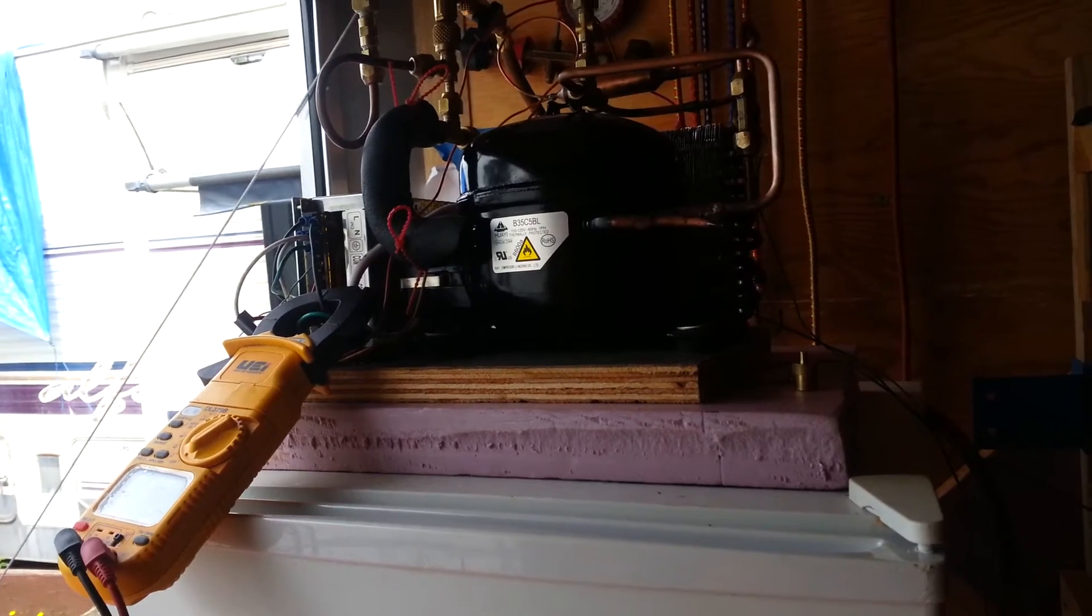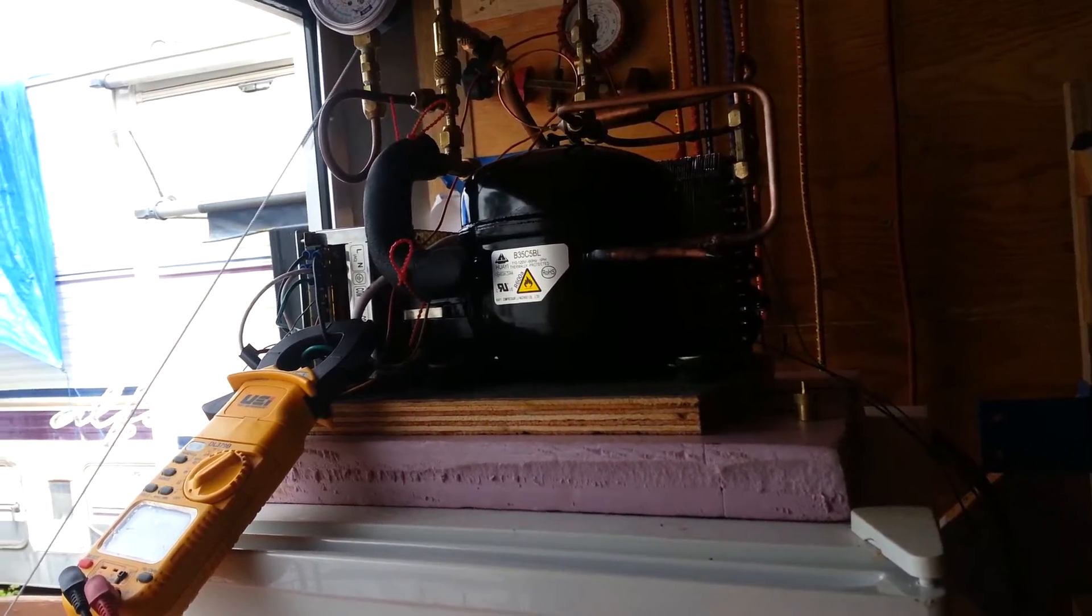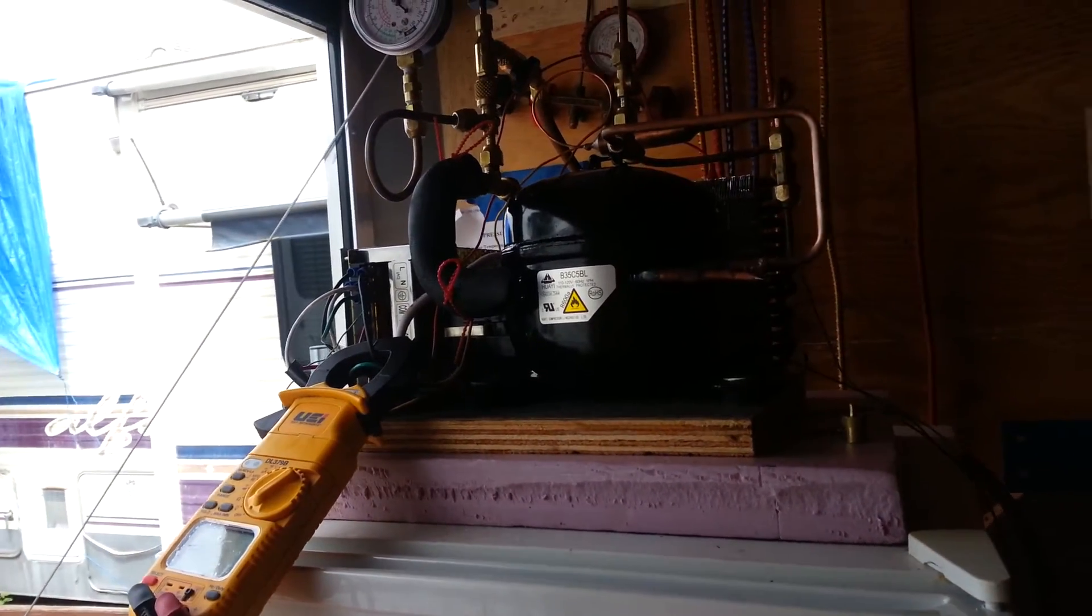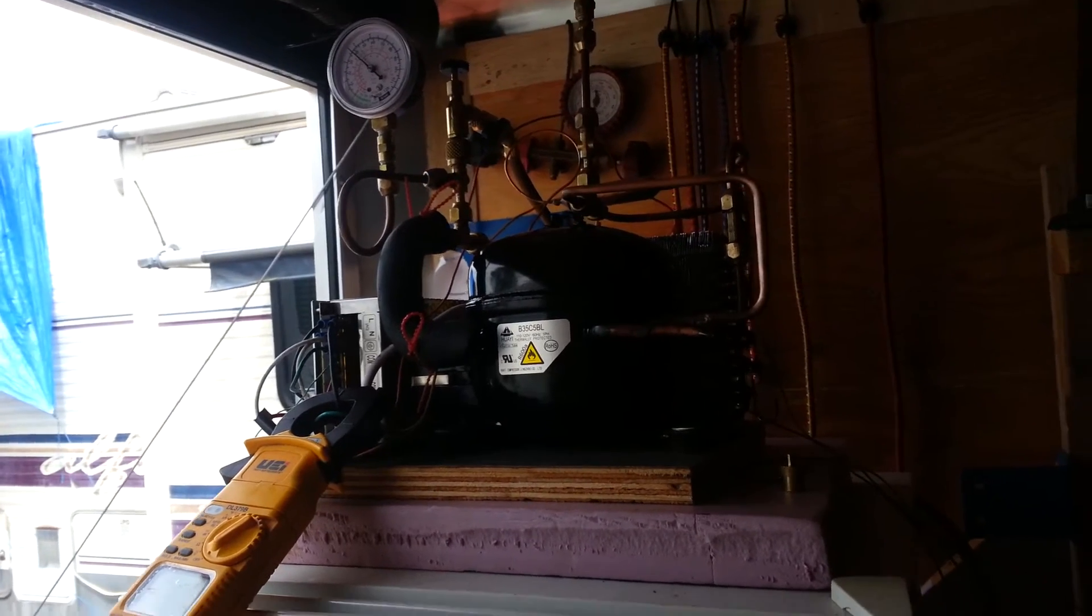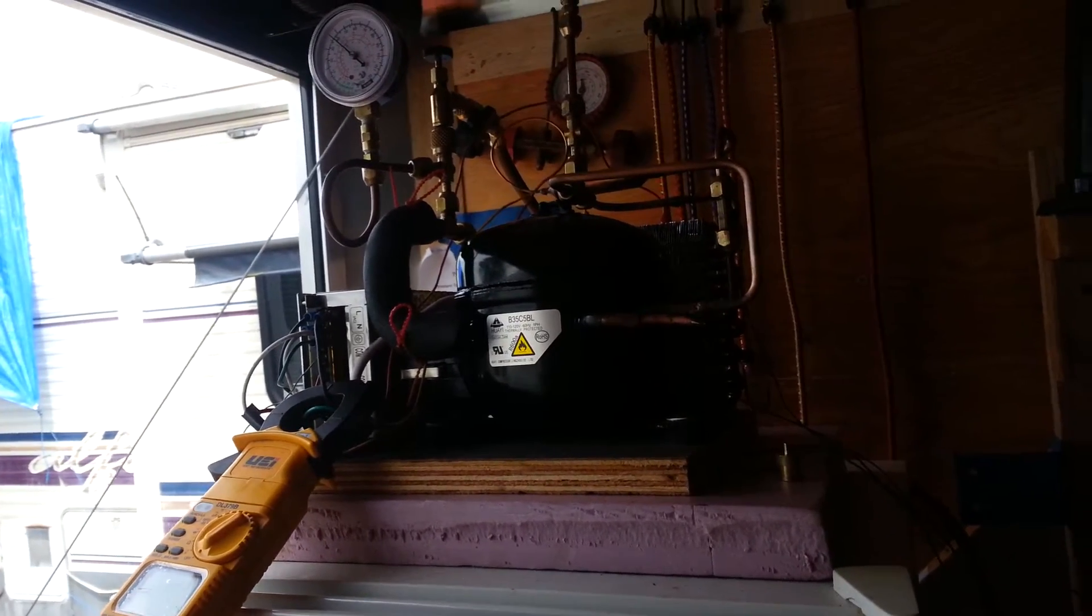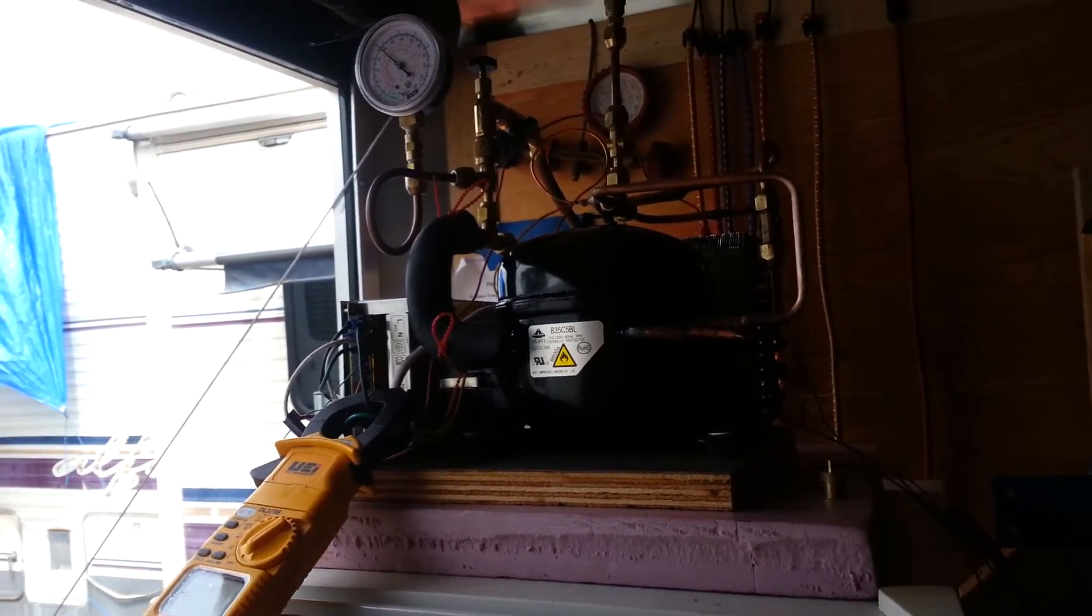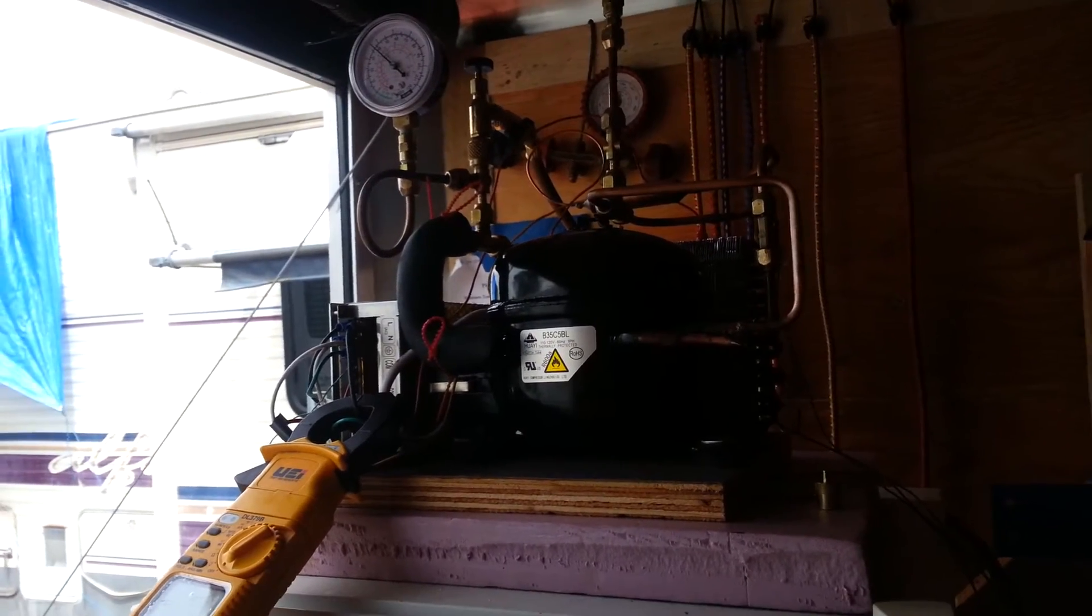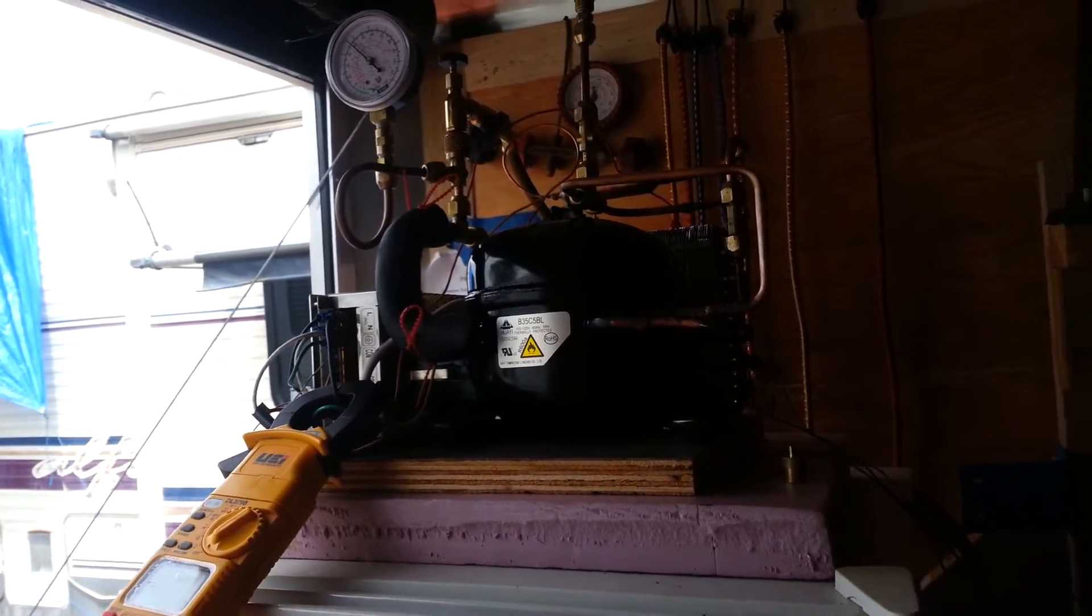Pulls about anywhere from 0.9 to 0.95 amp up to about 1.1 amp. When I tripped that thermal, it was up over like 1.3. I couldn't react fast enough before it tripped. Got her back in line. Don't know the exact charge yet.